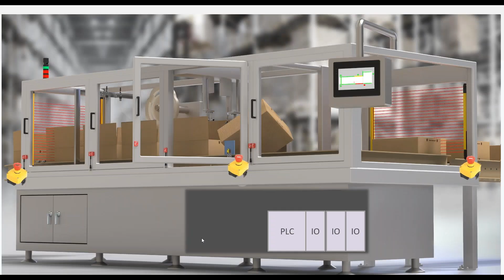Now, if we go into a little more complicated machine, this packaging machine has, I believe in this case, like 5 or 6 door switches. It has like 4 or 5 E-stops on it and 2 safety light curtains. In this case, you'd end up with 4 safety relays. The reason for that is each light curtain is tied to its own safety relay. Then, depending on how they're setting things up, the E-stop chain would have its own relay.